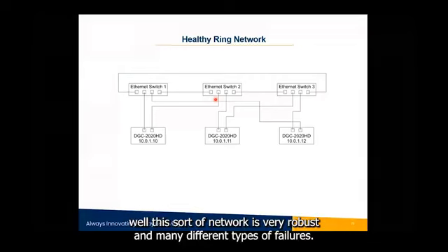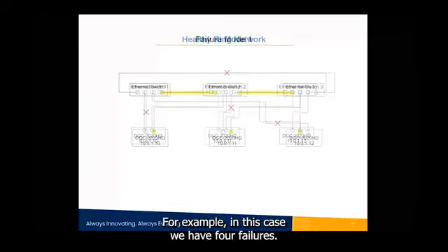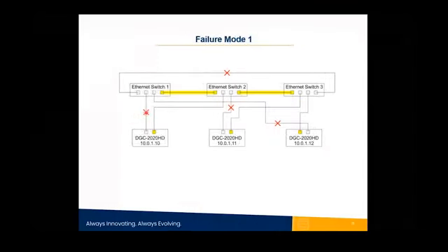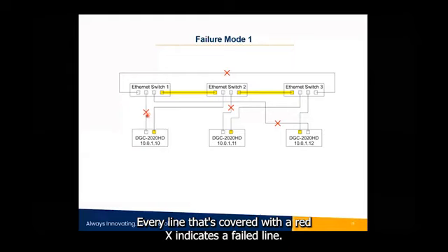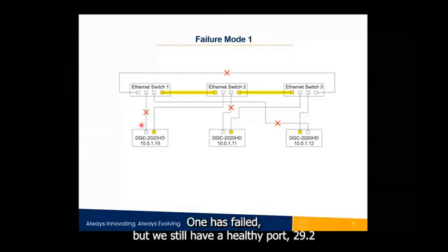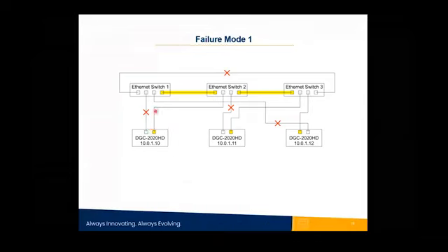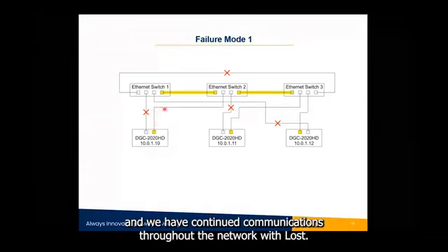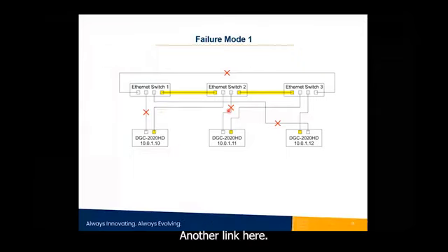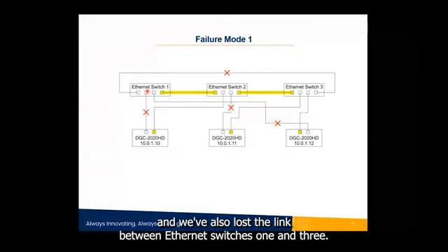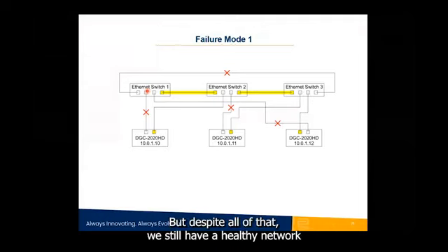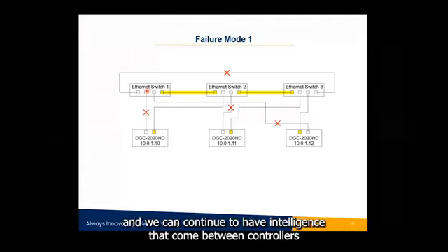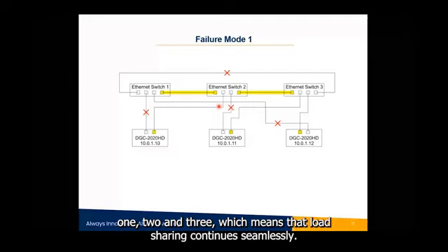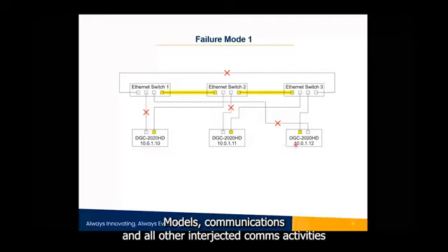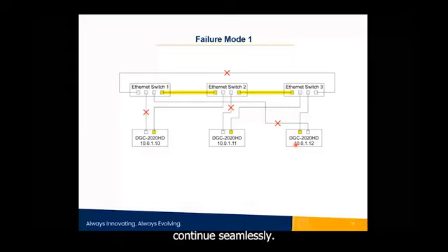Well, this sort of network is very robust to many different types of failures. For example, in this case, we have 4 failures. Every line that's covered with a red X indicates a failed line. So here, Ethernet port 1 has failed, but we still have a healthy port on Ethernet port 2. And we have continued communications throughout the network. We've lost another link here, we've lost a link here, and we've also lost the link between Ethernet switches 1 and 3. But despite all of that, we still have a healthy network, and we can continue to have inter-genset comms between controllers 1, 2, and 3, which means that load sharing continues seamlessly, Modbus communications, and all other inter-genset comms activities continue seamlessly.